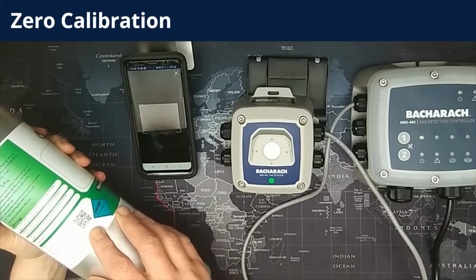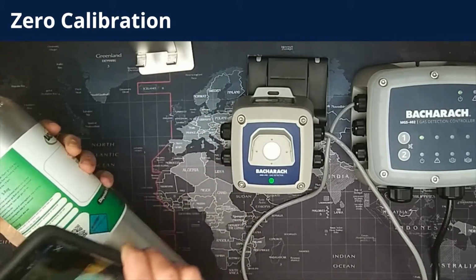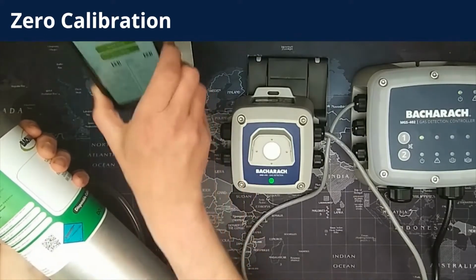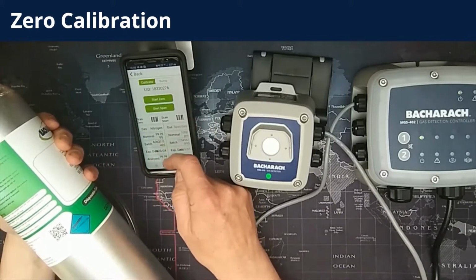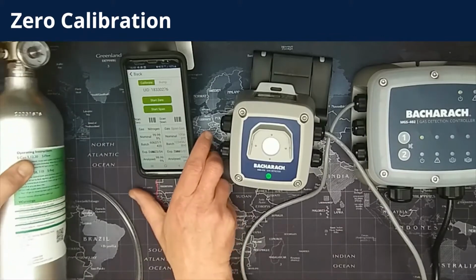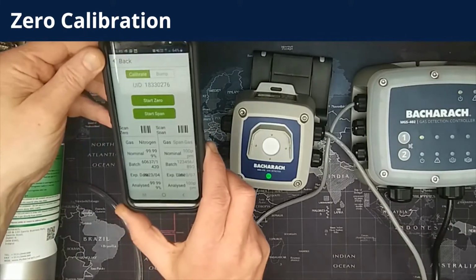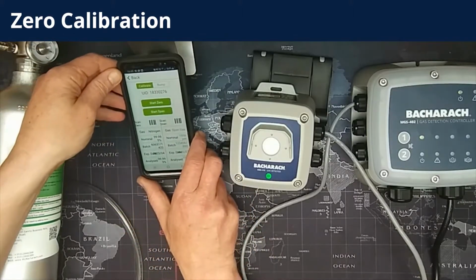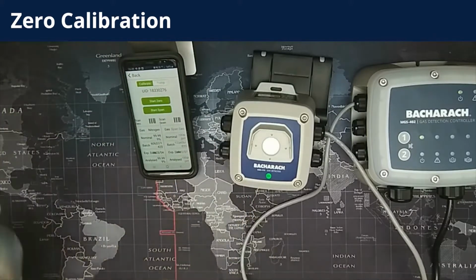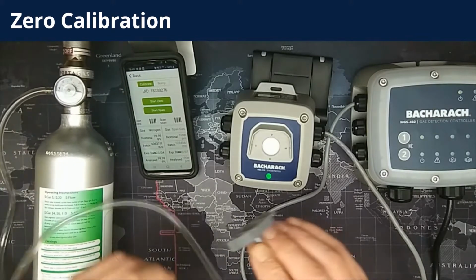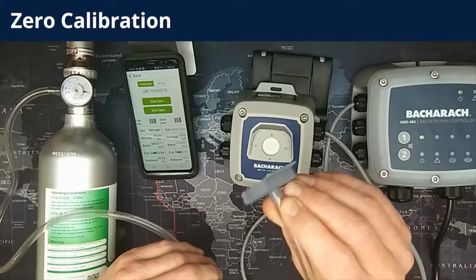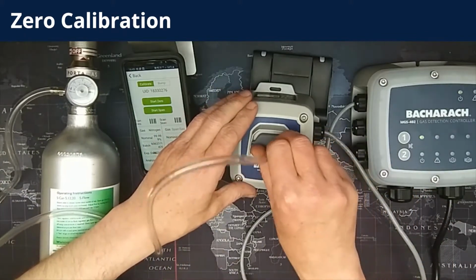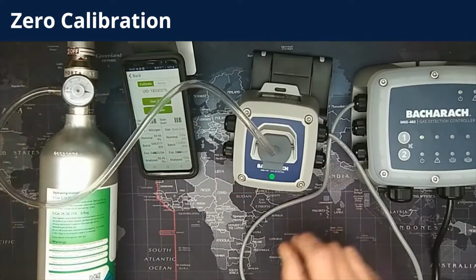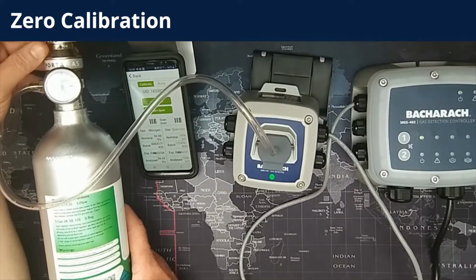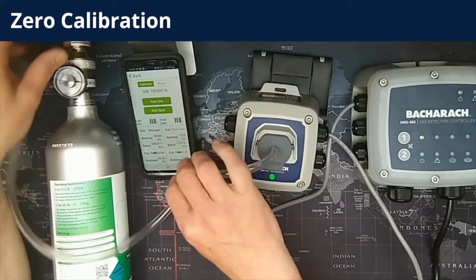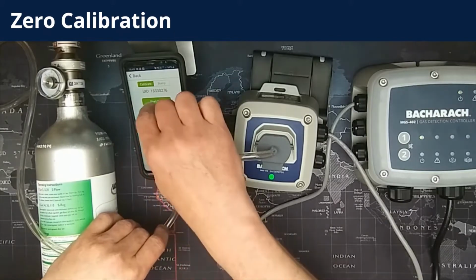You then press the Scan Zero barcode and scan the QR code on the side of the zero gas cylinder. That enters all of the zero gas data into the app on the calibration screen, and that information is used to produce the calibration certificates at the end of calibration. There you can see all the data has been entered. Then you need to fit the calibration adapter to the detector. Note that it only goes one way up, and it slots into the 2 slots either side of where the sensor is fitted. The next thing that you need to do is to select Start Zero on the calibration screen.